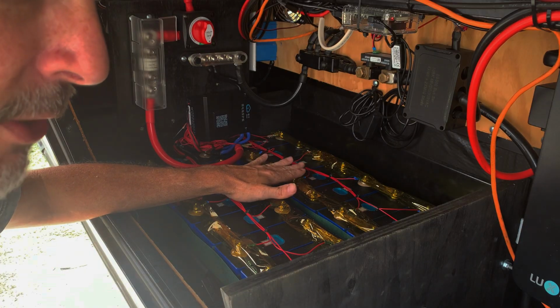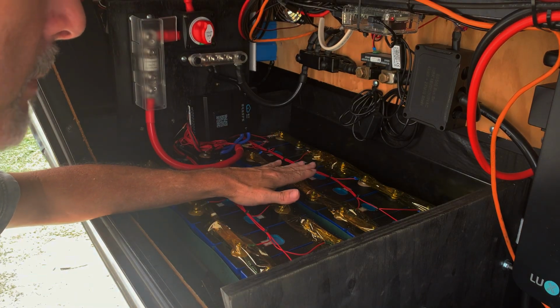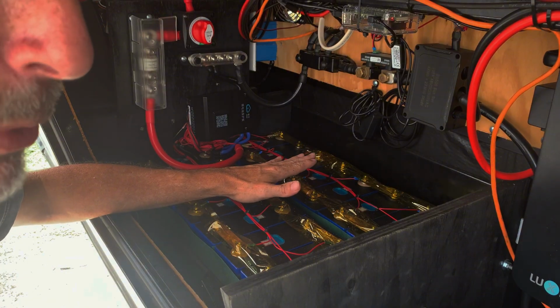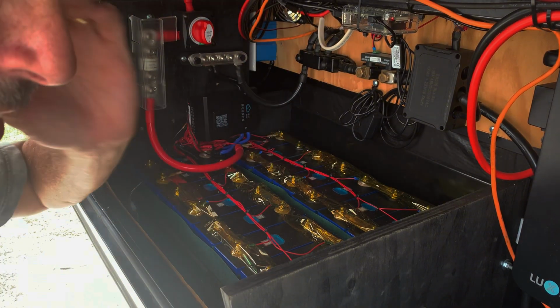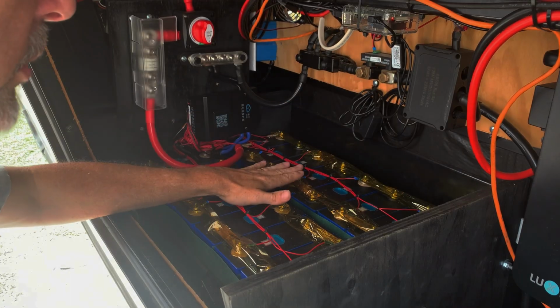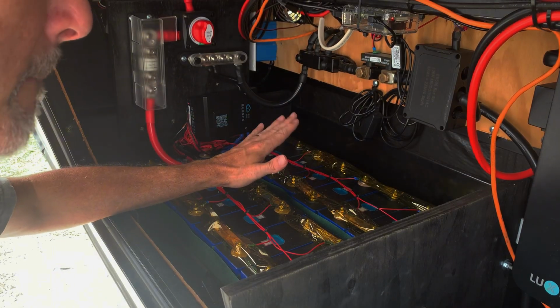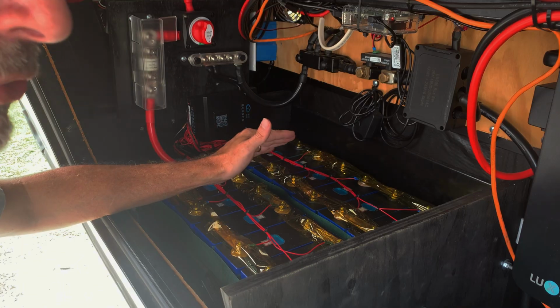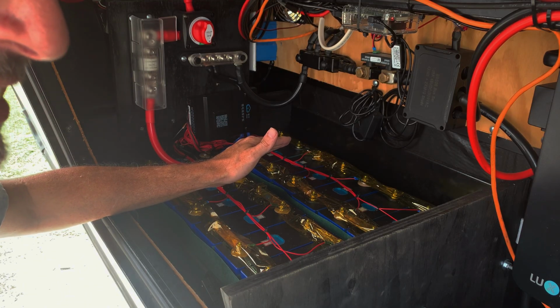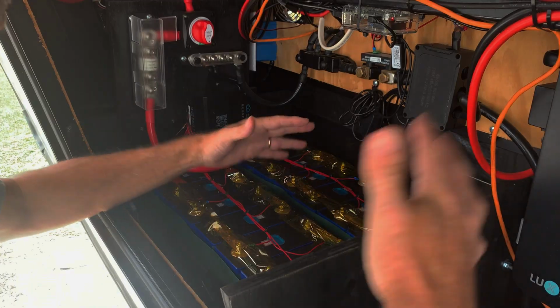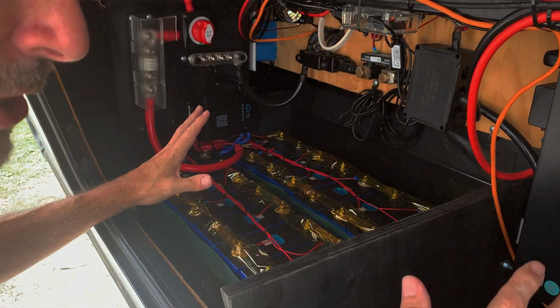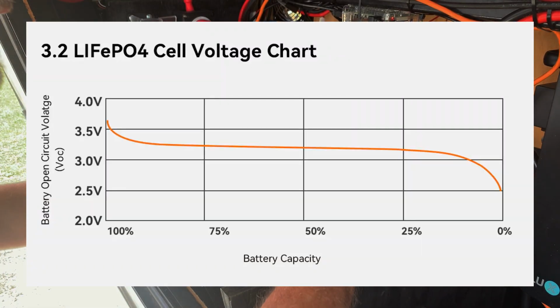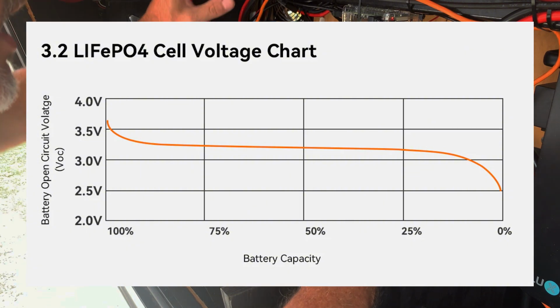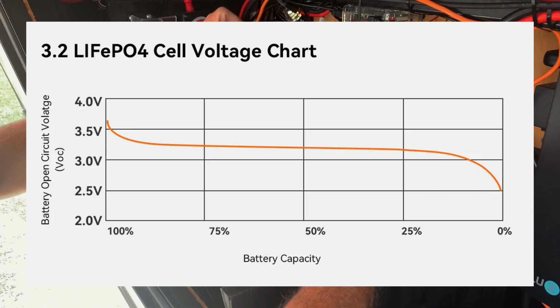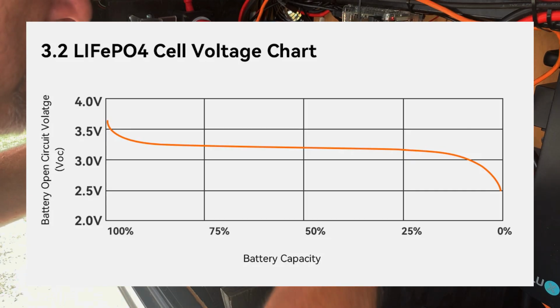If you take 304 amp hours, it comes out to roughly 15.6 to 16 kilowatt hours at 51.2 volts. We use 51.2 volts because that's the standard voltage of the battery in its Goldilocks zone, not at the arms and legs at the beginning and end. I'll show you a chart where the first 10% of a battery is where the voltage really spikes up, and the last 10% is where it really dips off.